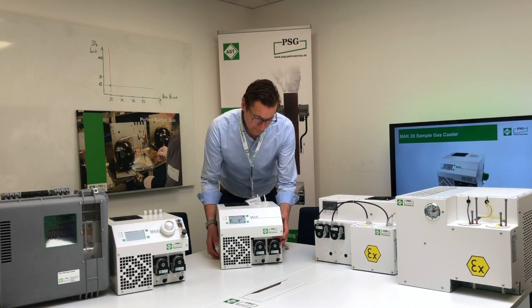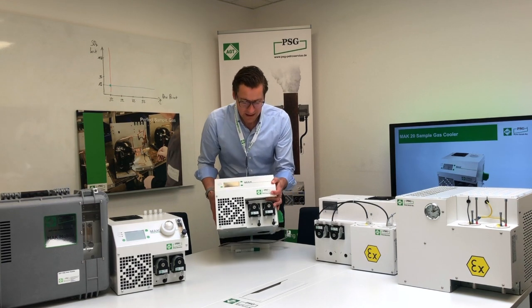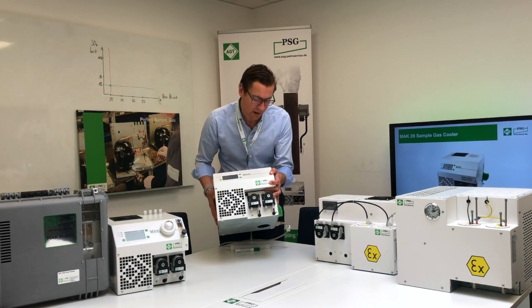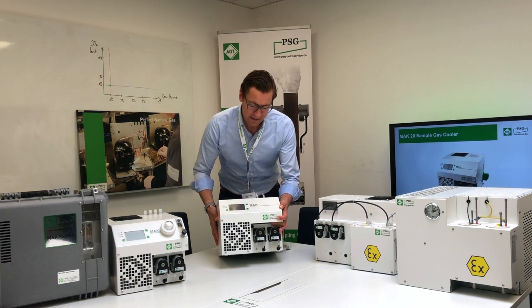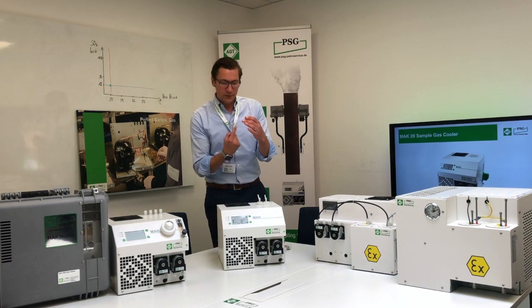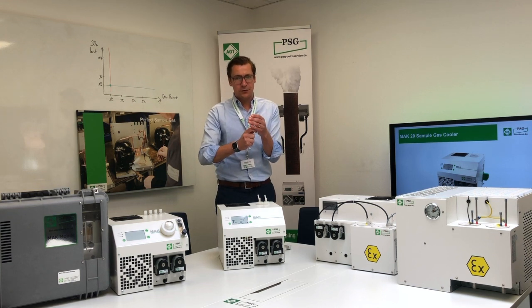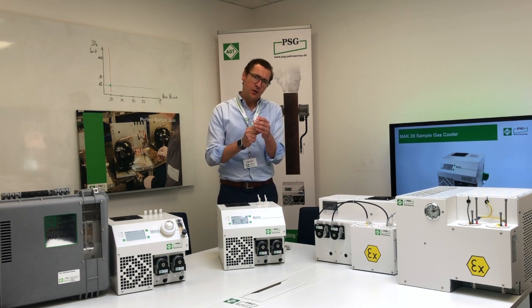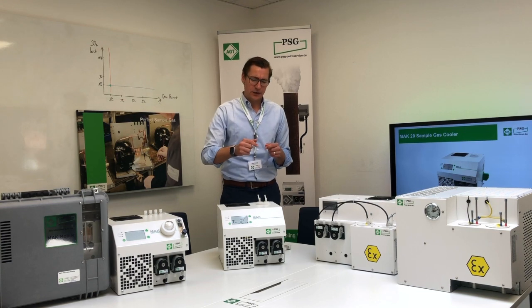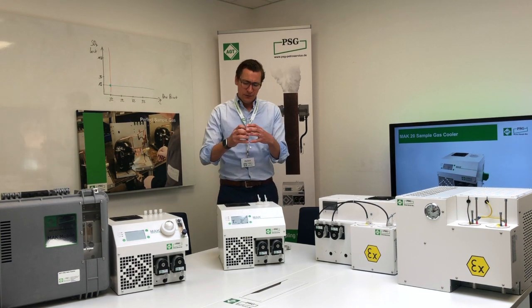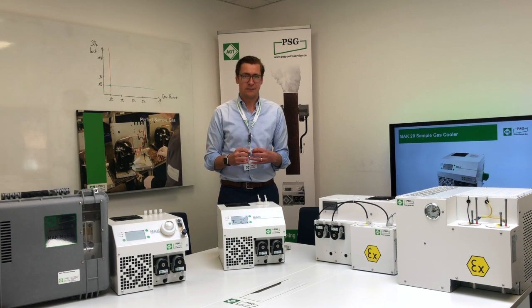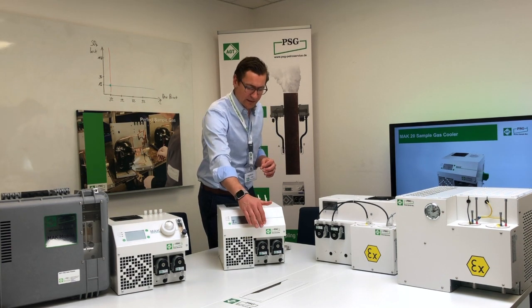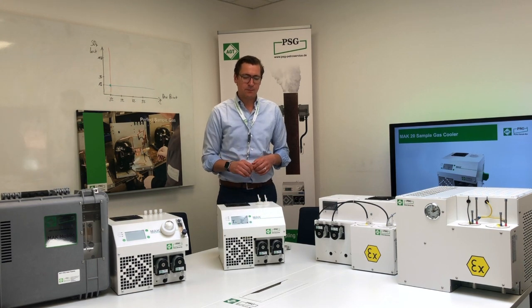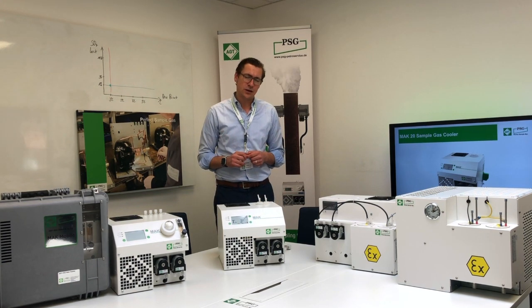You can also see there's a hole at the bottom of the MAK-20, which lets you remove the tubing for the condensate connection for the peristaltic pump, and you can also use this as a drainer. So if you don't want to connect to the peristaltic pump, or want to use a different heat exchanger, there's no problem—you can easily do this.